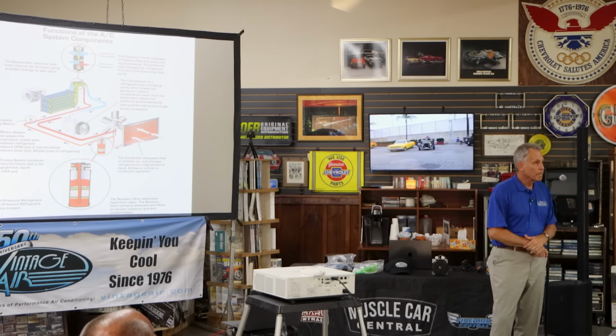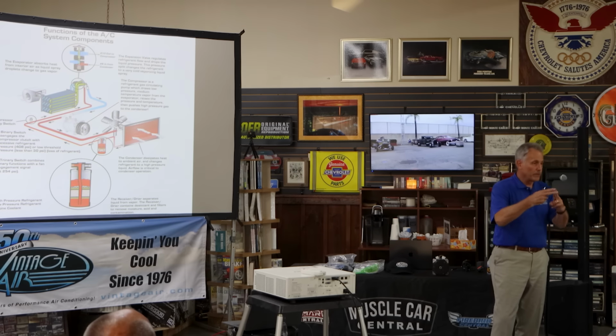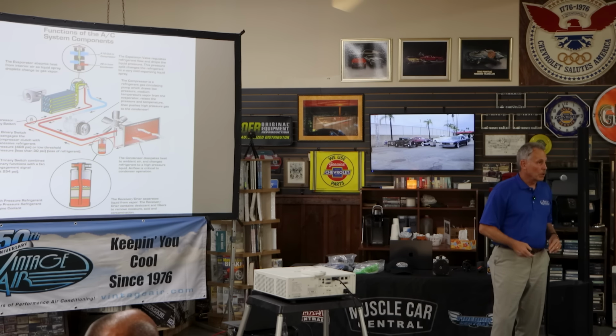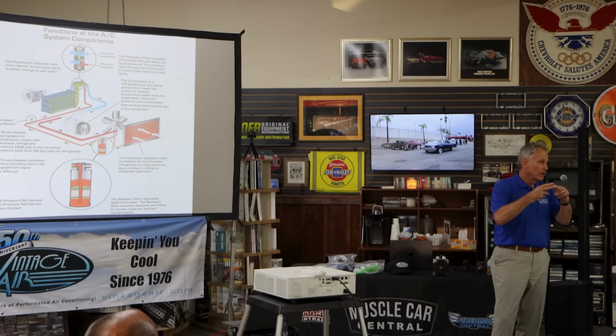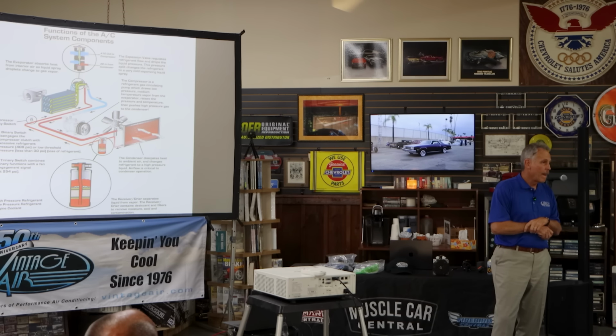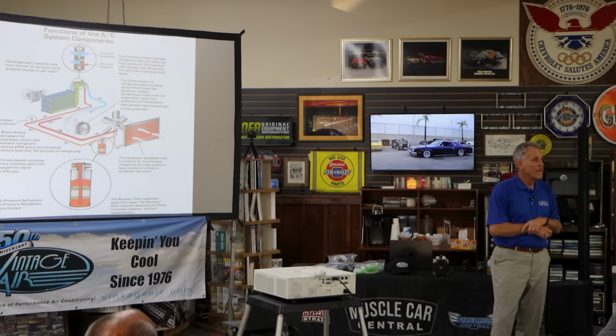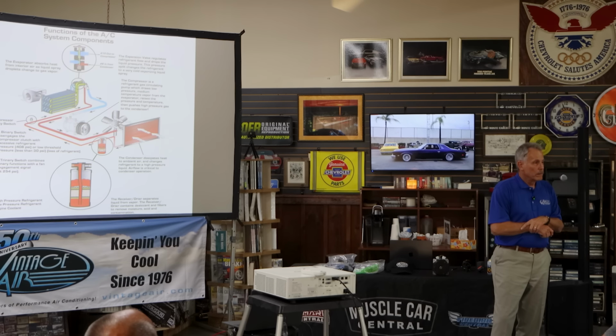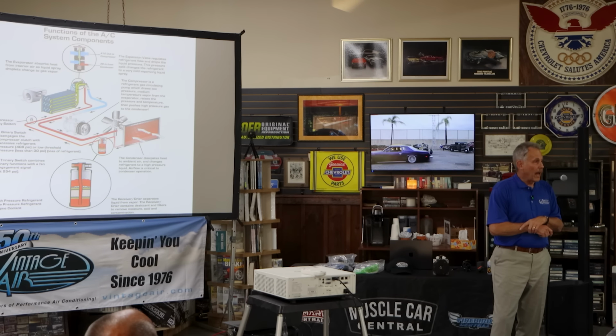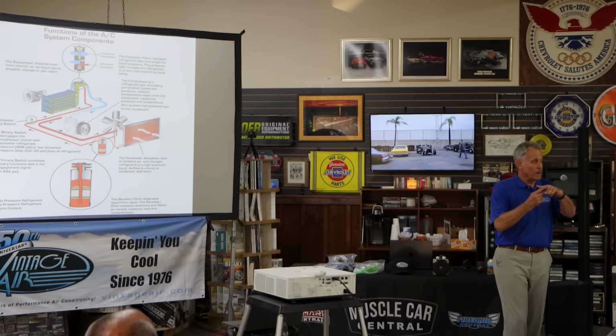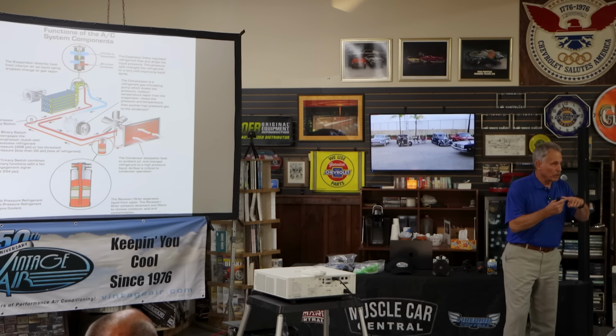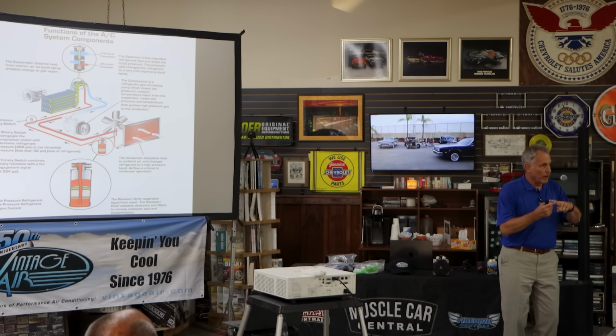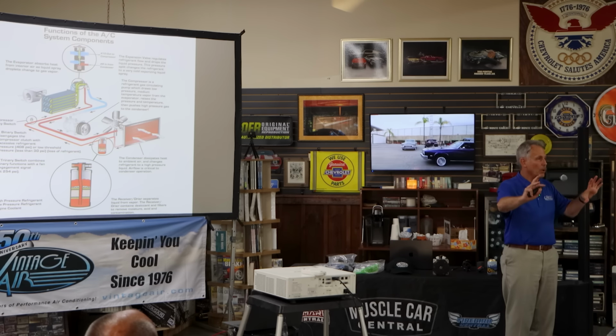So would I have to go back and rewire that? You'll have to join them together, put a Y connector on those two fans, so they're set to the same temperature instead of different ones. I'd just mechanically put the two power wires of the fan together and run them to that same output, so whatever output you set, it turns them both on.